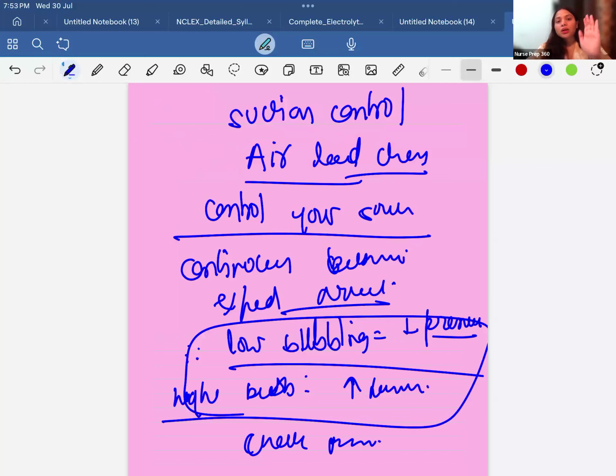Whenever you open a chest tube box, there will be water given in a chamber, so you need to pour that in the water seal chamber. There is a port where we pour water into the chamber. Depending on the company, maximum 20 ml water is kept in that bottle.